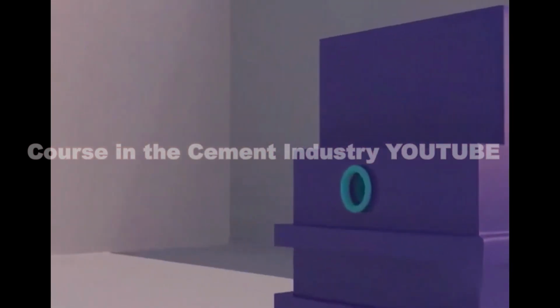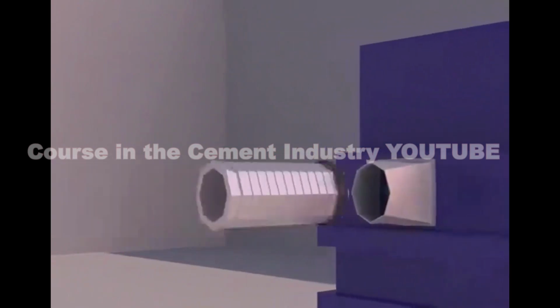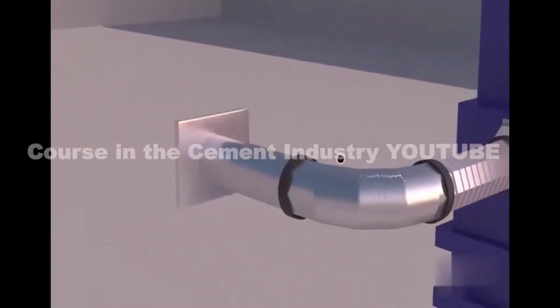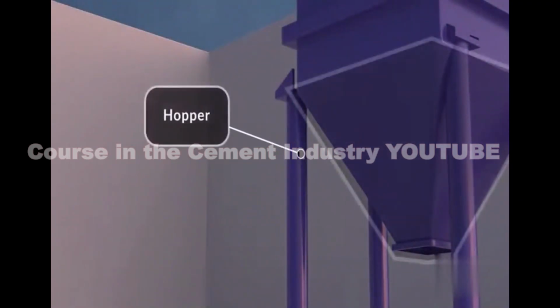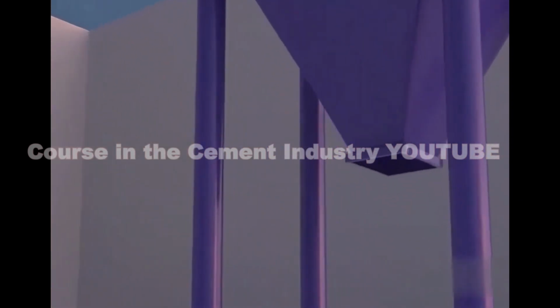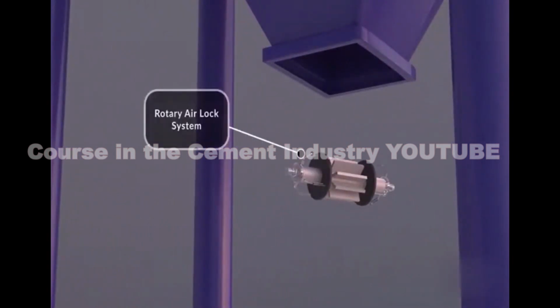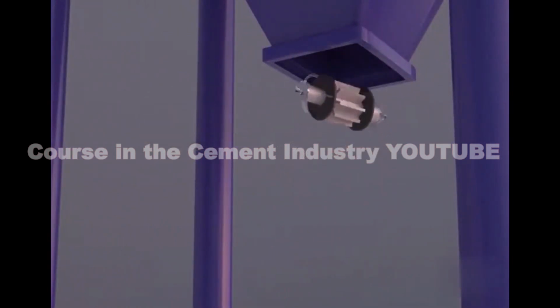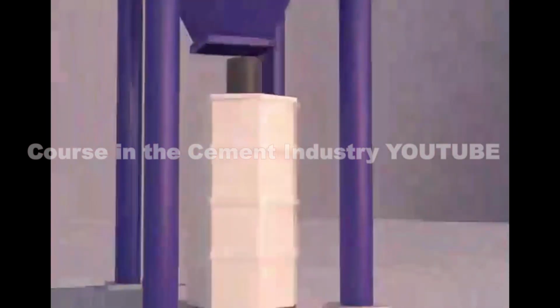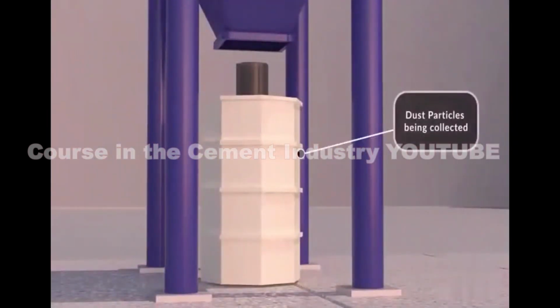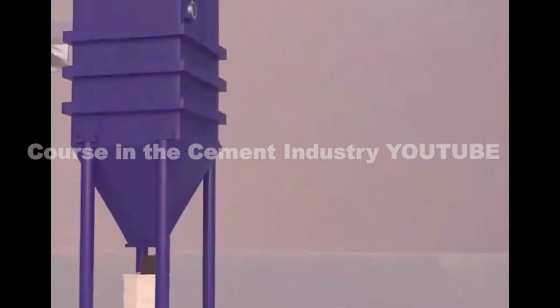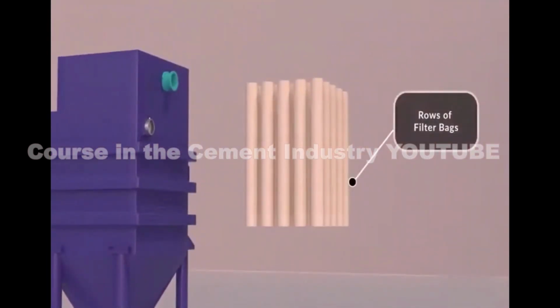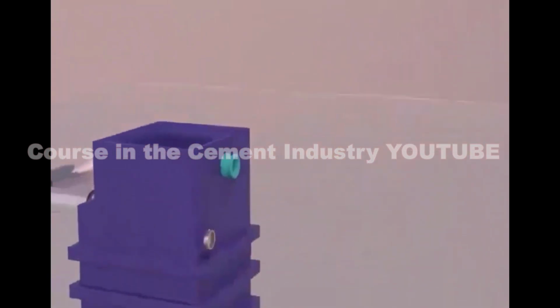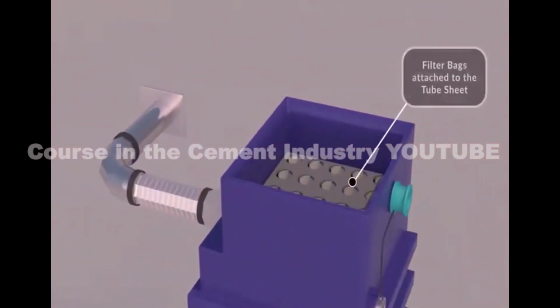The lower body includes an inlet which is connected to flexible suction pipes which carry the dirty air from the source. At the bottom is a hopper, which is fitted with a rotary airlock system for continuous discharge of dust particles. The lower body includes the main filtration system. This includes rows of filter bags. Each filter bag is attached to the tube sheet.